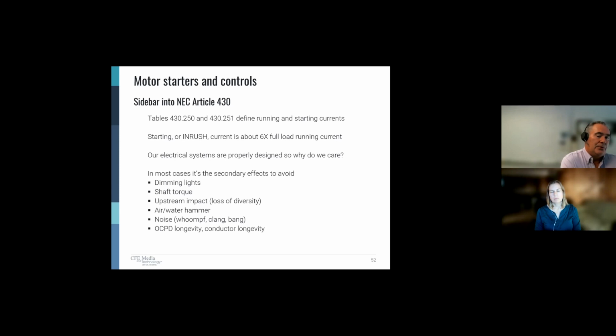If we design our electrical systems properly, why do we care about inrush current? Well, we care because it's the secondary effects we want to avoid. You know, back in the day, the fan would start and the lights would dim. Well, that would be kind of annoying. We're concerned about the shaft torque. We don't want to, you know, overly stress that shaft if we can avoid it. Eventually, you know, it will fail.